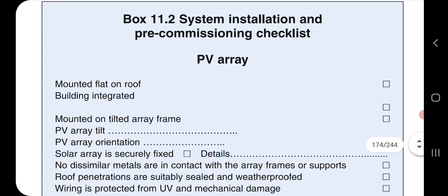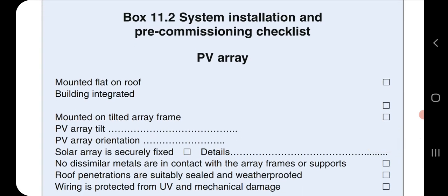In this one, they have given an installation and pre-commissioning checklist. You can see there are various types of things in this one. They will check all the things in the PV system or equipment. They are going to check it all, and they'll make a checklist for things like mounting flat on a roof, building integrity, PV array tilted, and solar array fixed.